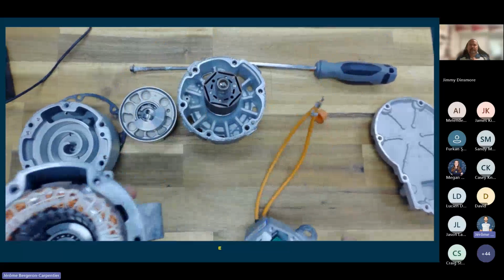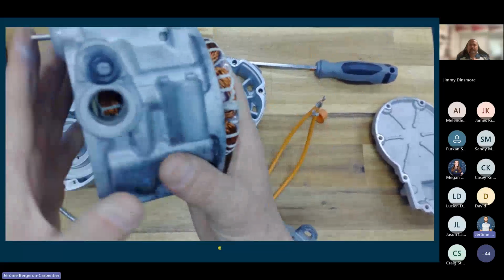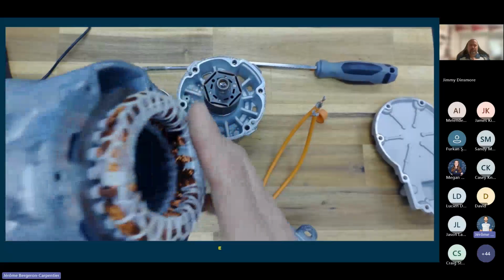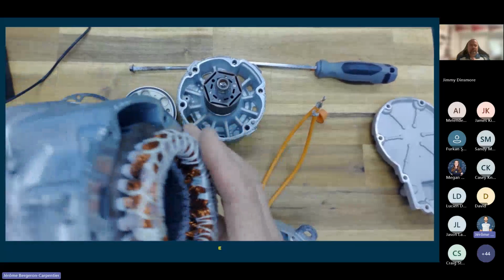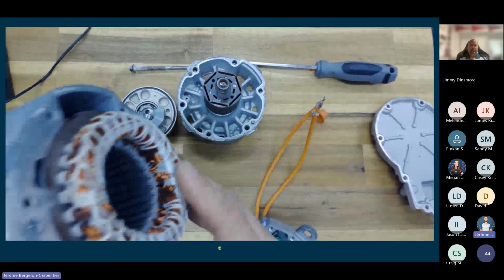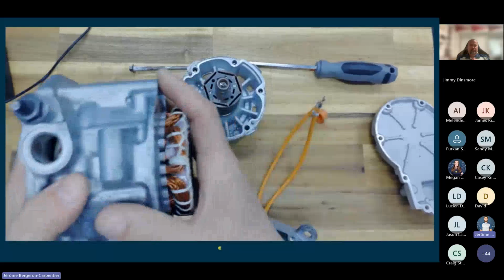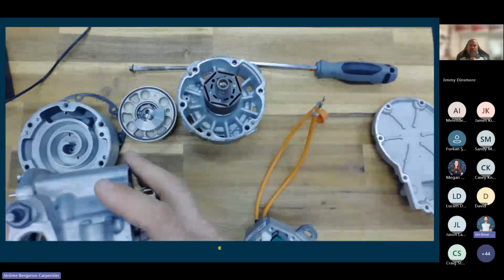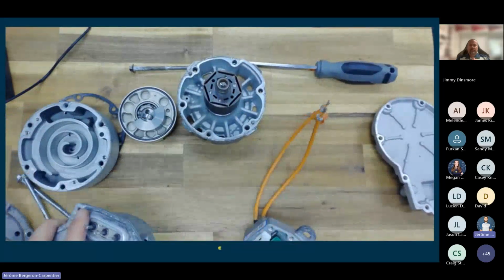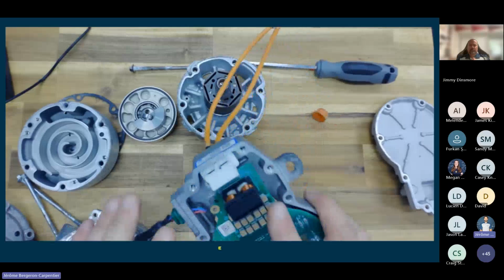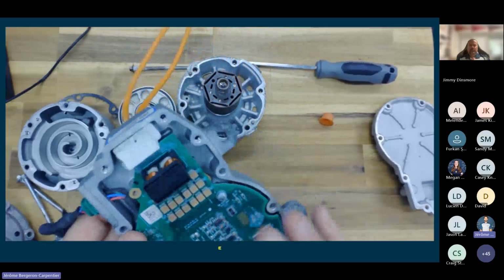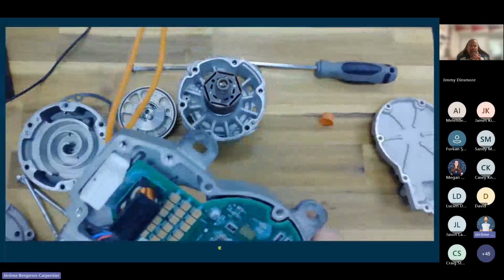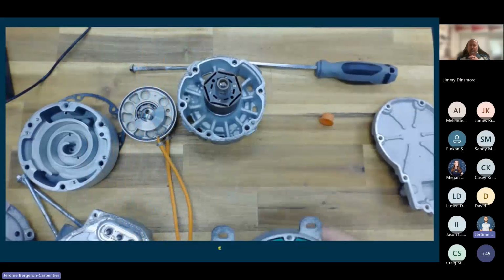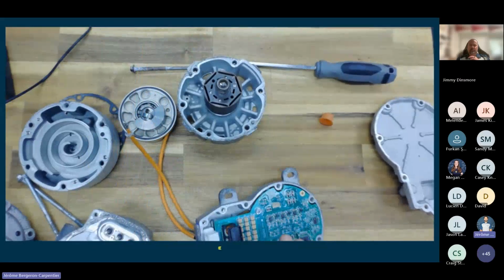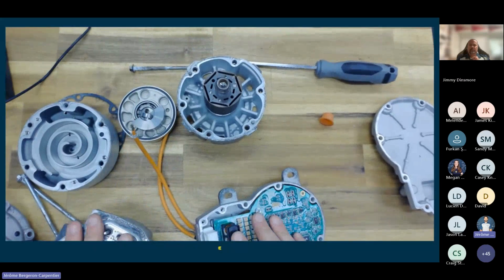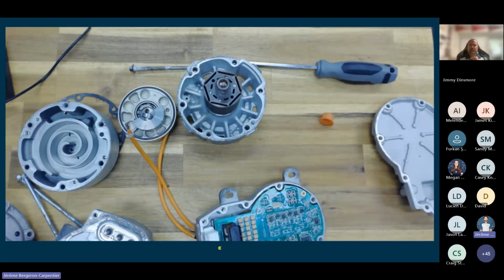At this point here, I could definitely do an isolation test to this unit from each of the legs of the stator, looking for which one is bad here. But obviously, we're not going to be tearing apart compressors and testing them directly at the stator. We'll rely on codes and OEM test procedures when we're testing these compressors for those types of faults. Okay, so one last thing I want to do is go back to the video. I know this is fast. We're just going through it.